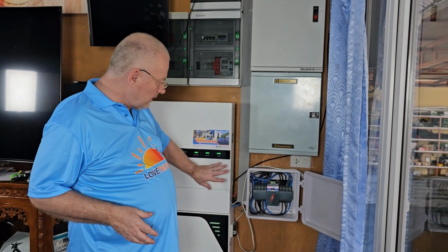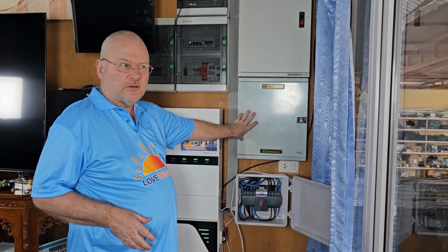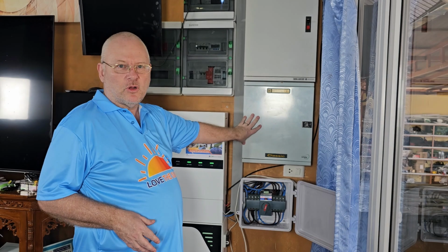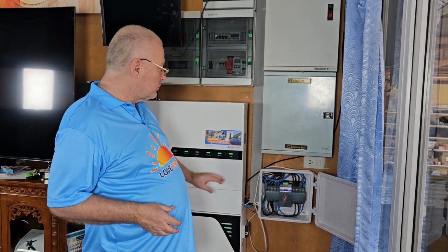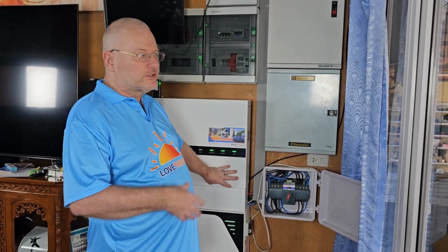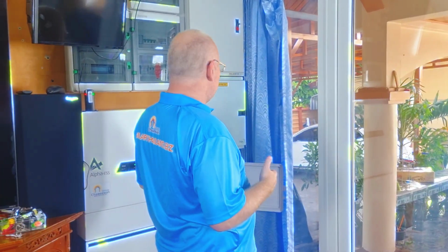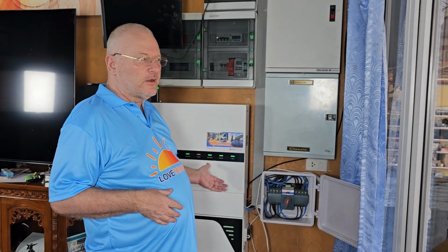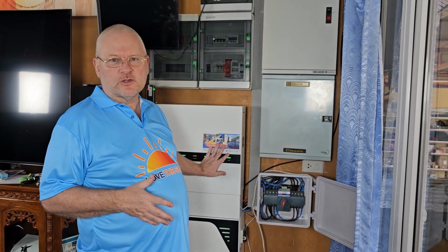If it doesn't have an ATS, when the solar system for some reason has a failure, you will not have power in the UPS panel. So you will lose all the essential loads, which is not the way an installation should be. You should always have an ATS, so that if there's a failure in the solar, which can happen because of something bad on the grid, and then it must shut down or it has a fault because of something. Solar systems are not perfect. It can go into fault sometimes.